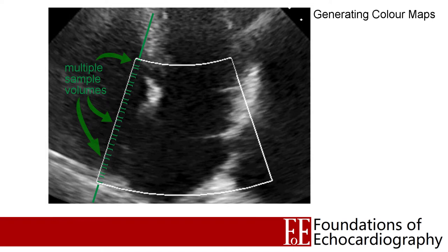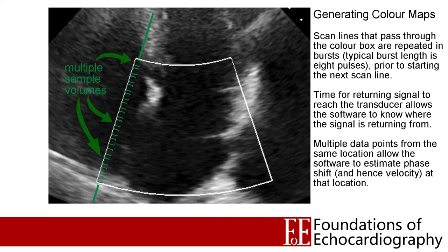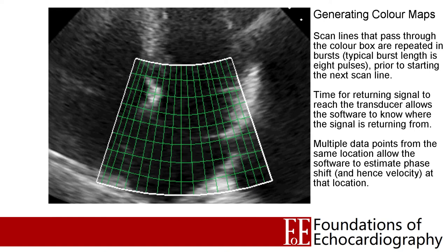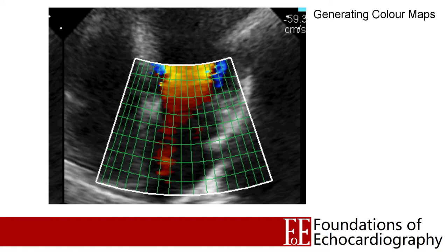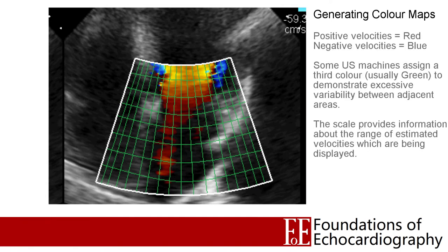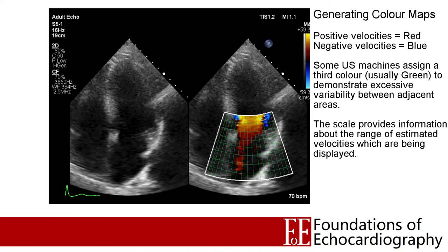It can't estimate phase shift from a single piece of information — it requires multiple values from the same location. So those scanlines that pass through the box are rapidly repeated, typically around 8 times, before moving on to the next scanline. Once there's been enough time for the scanline to sweep through the colour box, we end up with a grid of estimated velocities which can then be represented as a colour. By convention, positive velocities moving towards the transducer are represented with a shade of red, whereas negative velocities away from the transducer are represented with shades of blue, with brighter shades representing faster velocities.